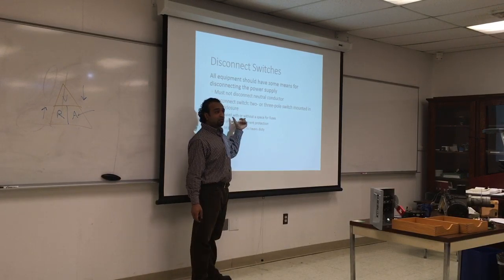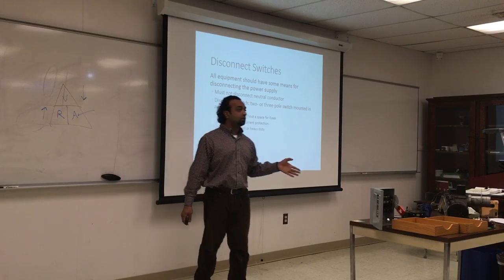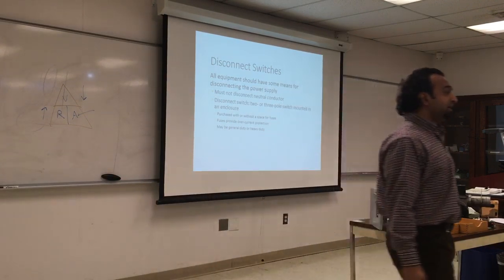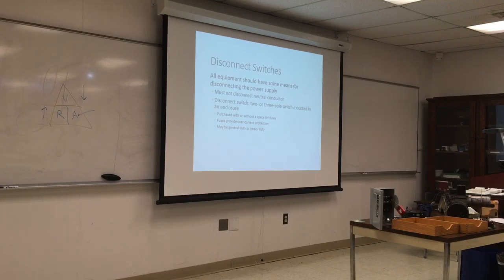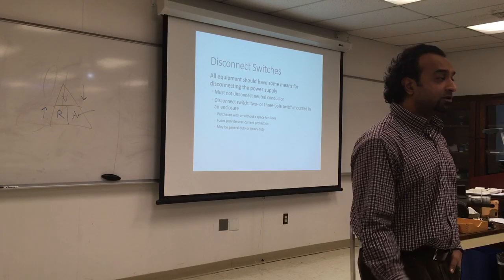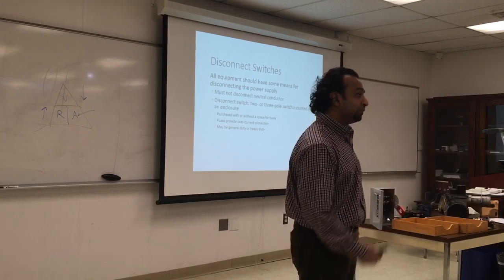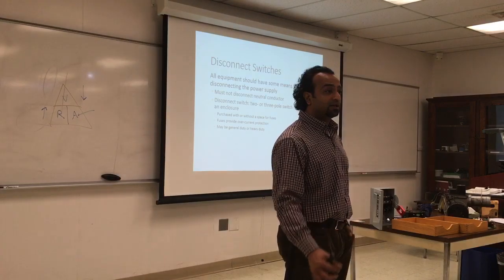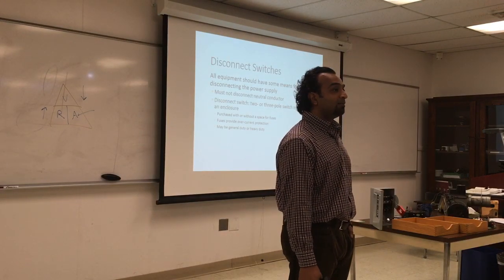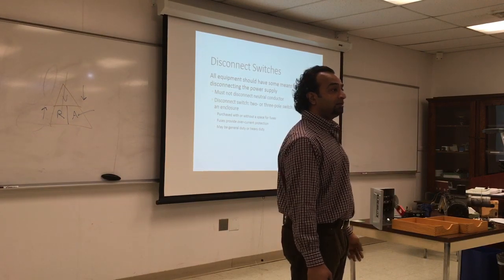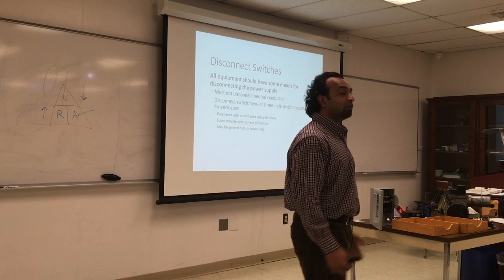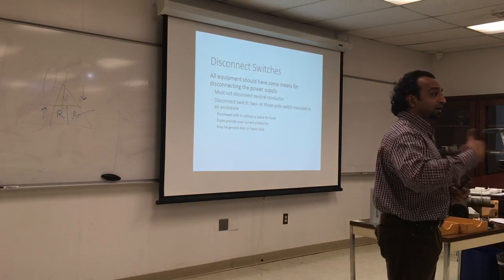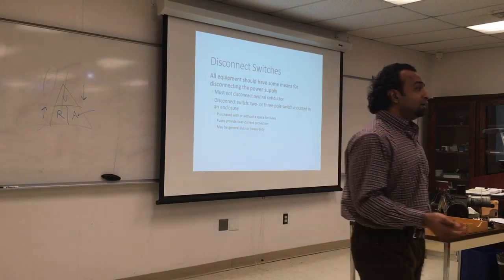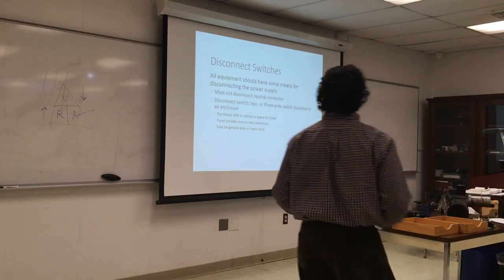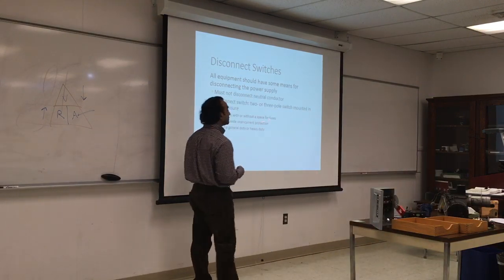So some of them are fusible, some of them are not fusible, depending on what you are going to use it for, and what is the recommendation for that equipment. Sometimes with large compressors, you do not want to use a fuse. Why? They account for the startup of the compressor that might spike the power, and if you have a fuse, you'll burn the fuse every time you try to start the compressor after a long time of rest. Do you notice that sometimes you have a pump, a water pump, an oil pump sitting for a long time? When you turn it on, it's not going to turn because it's been sitting for a long time. So sometimes it will spike a lot of power. So if we have a compressor that has not been running the whole season, then we try to turn it on, it might burn the fuse. So check with the recommendation for the fuse whether it's going to require a fuse or not.